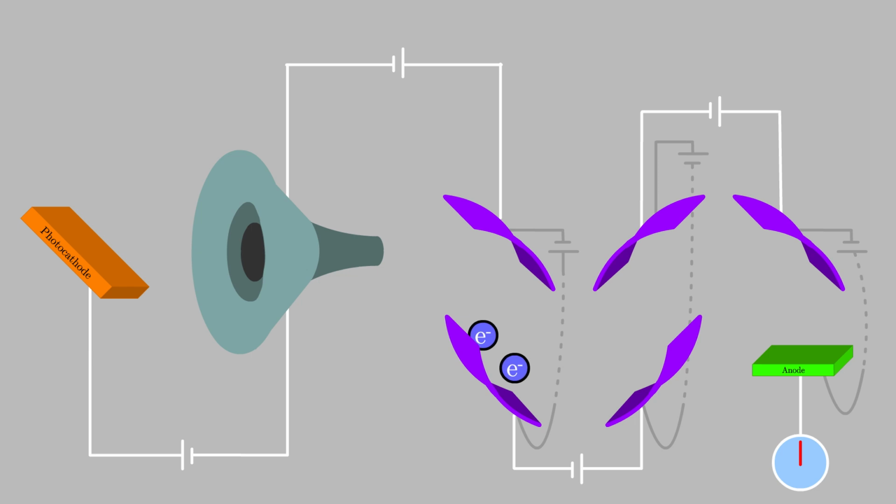To multiply these newly ejected electrons, we use a second dynode with an even higher positive potential. It pulls the electrons from the first one. Again, they collide with high kinetic energy, ejecting even more electrons. This cycle repeats down to the final dynodes. After the electrons are ejected from the final dynode, the anode pulls them with the highest potential in the entire tube.